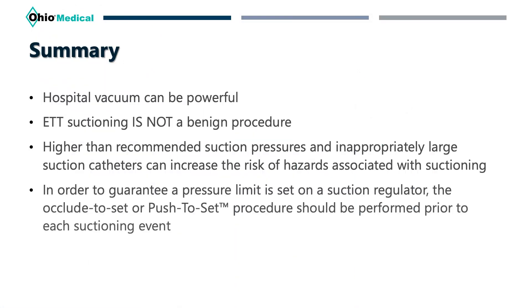To summarize: one, hospital vacuum can be very powerful; suctioning an airway is not a benign procedure. Higher than recommended suction pressures and inappropriately large suction catheters can increase the risks or hazards associated with suctioning. In order to guarantee that a pressure limit is set on a suction regulator, either the occlude to set or push to set procedure should be performed prior to each suctioning event. Thank you for watching this presentation.